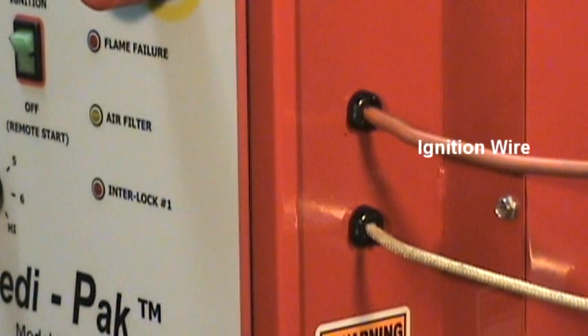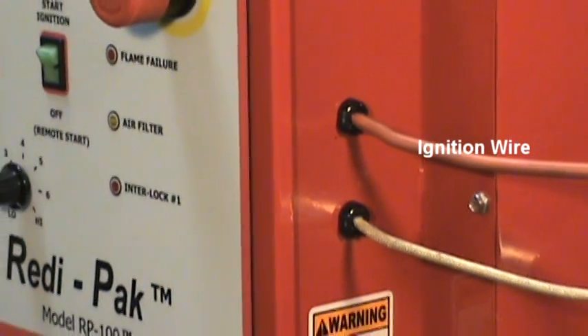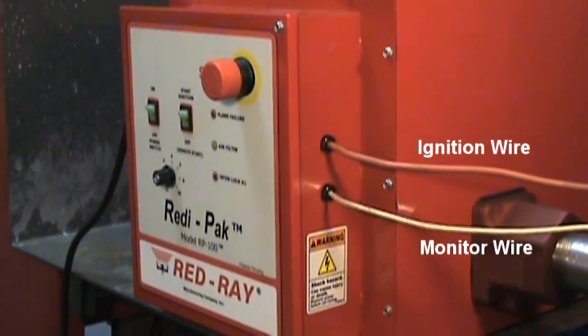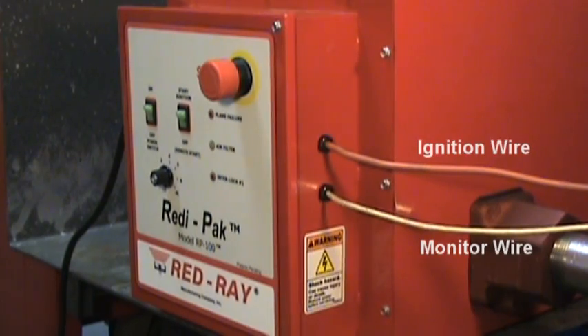The ignition wire exits the control box and leads to the spark igniter. A flame electrode at the burner constantly monitors the presence of flame signal, which is sent back to the Redi-Pak by way of the monitor wire.